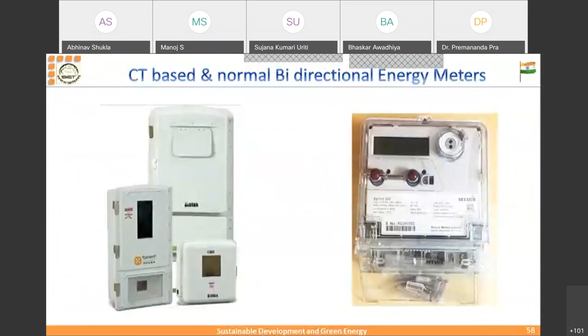CT based and bidirectional meters are there. These are the components list, and there is a checklist for the discom engineers. They will come and check the entire thing, and they will do the unintentional islanding functionality test. If there is more than one inverter, the test should be carried out for each inverter.